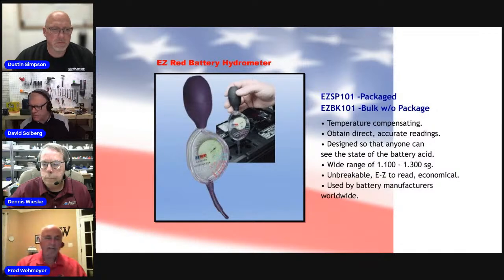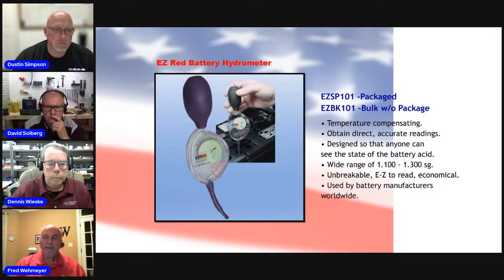The nice thing about that is you can check each individual cell. So if you see a cell starting to get weak, you'll see a lower specific gravity in that cell. It's also a good indication of when you need to equalize, because if you see a variation among the cells in one or more batteries, it's probably a good indication that it's time to equalize.